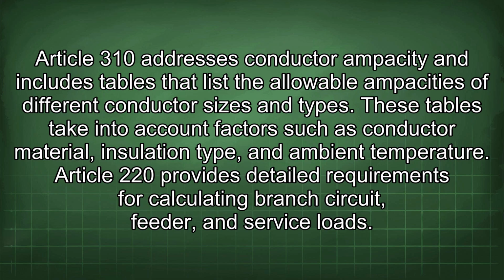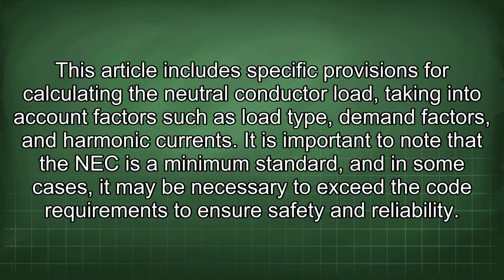Article 220 provides detailed requirements for calculating branch circuit, feeder, and service loads. This article includes specific provisions for calculating the neutral conductor load, taking into account factors such as load type, demand factors, and harmonic currents. It is important to note that the NEC is a minimum standard, and in some cases, it may be necessary to exceed the code requirements to ensure safety and reliability.